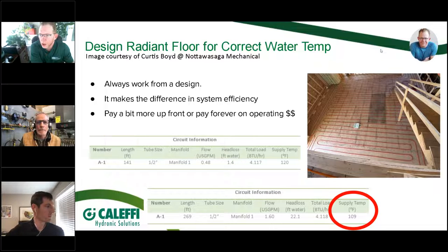We touched on this a little bit. A lot of people sort of go, well, it's great that Max keeps telling me to drive my water temperature down. That's just not achievable. And again, this photo was supplied to me by a good friend of mine, Curtis at Nottawasaga Mechanical. It's a real world scenario where he was faced with how do I get the water temperature down? So we showed him. And Curtis is the kind of guy that loves knowledge. The only thing that we changed is we changed the tube spacing from 12 inch to 6 inch spacing. And we drove that supply temperature from 120 degrees to 109 degrees.